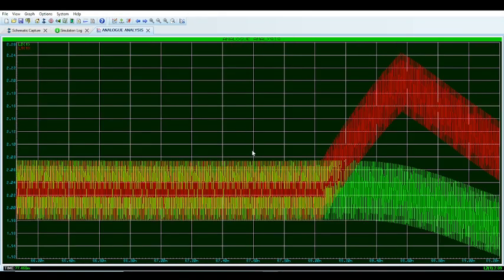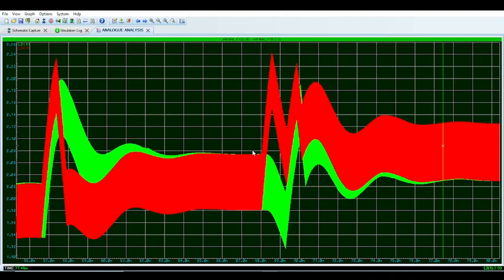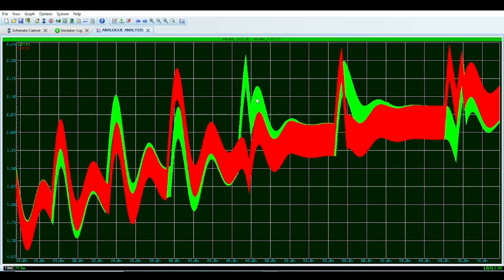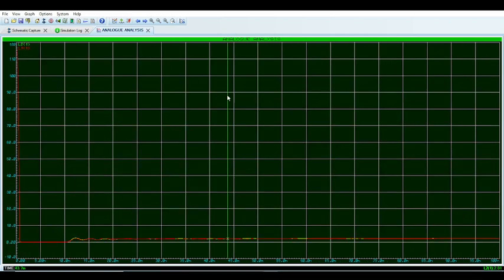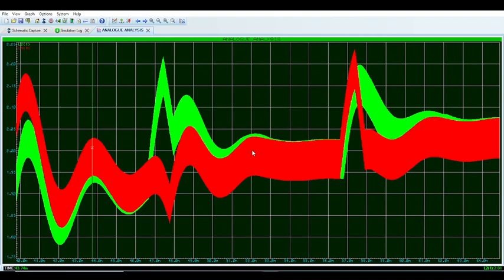Let me just check if it's done here. And right, the set point is 2.2, but it's not quite there. But as you can see, both are not gonna exactly look the same. I mean, it doesn't look the same on the simulation. You think it's gonna look the same in the real world? Absolutely not. That's why you have to control them differently. You need two different PID routines, routines for both of them individually.